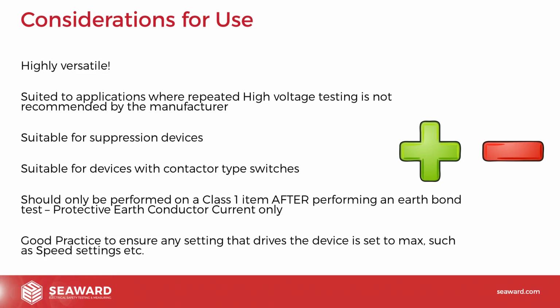For the protective earth conductor current test, very similar to previous guidance about the insulation resistance test. You should only perform this test on a class 1 item after you've performed the earth bond test. Again, just to repeat why, it's to ensure that the earth cable, which is part of the measuring circuit, is in place and doing its job. If it isn't there, we could get a reading of 0 leakage because there's nothing for that current to flow down back into the device to give us a good reading.